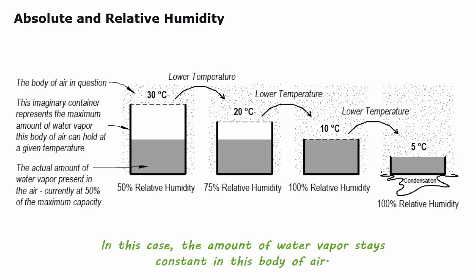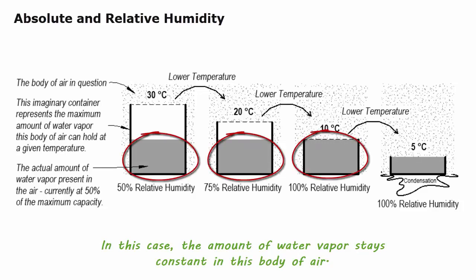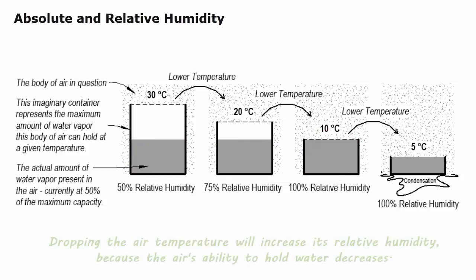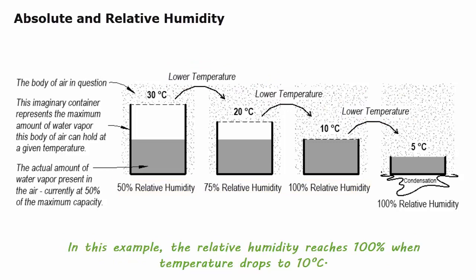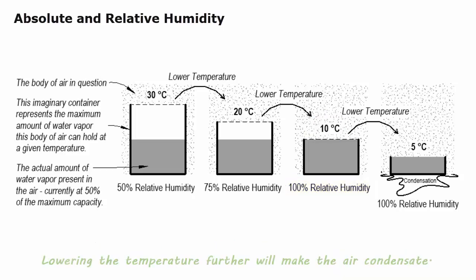In this case, the amount of water vapor stays constant in this body of air. Dropping the air temperature will increase its relative humidity because the air's ability to hold water decreases. In this example, the relative humidity reaches 100% when the temperature drops to 10 degrees C. Lowering the temperature further will make the air condensate.